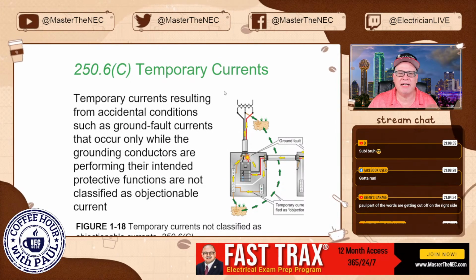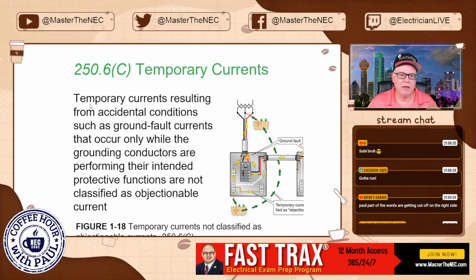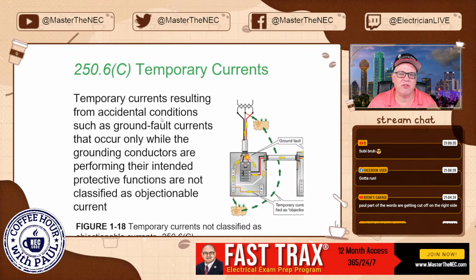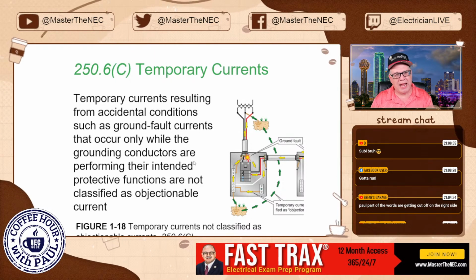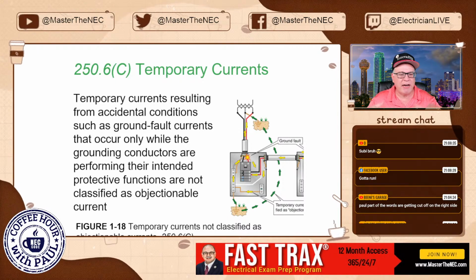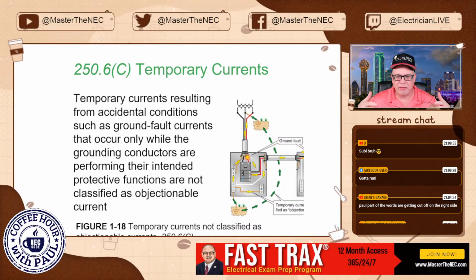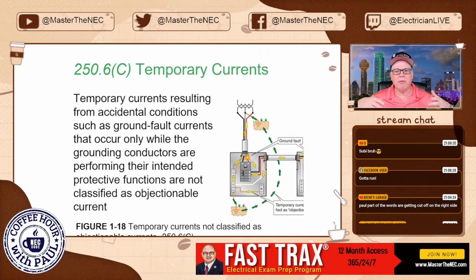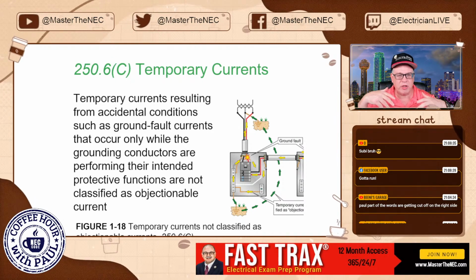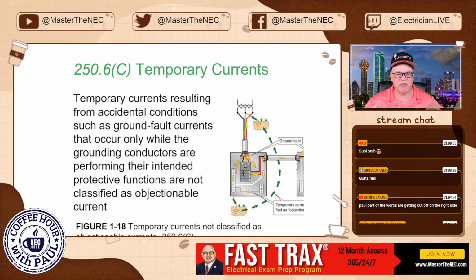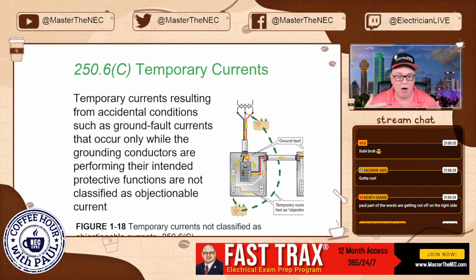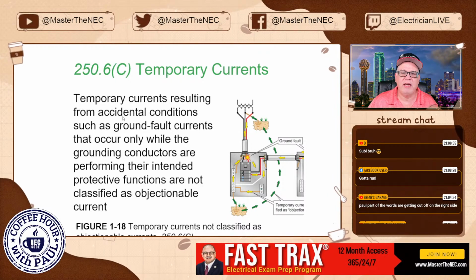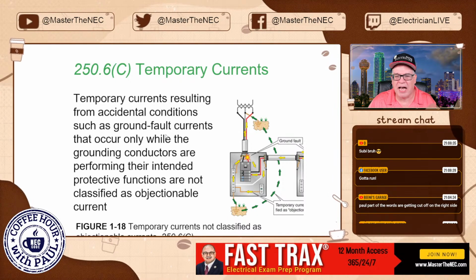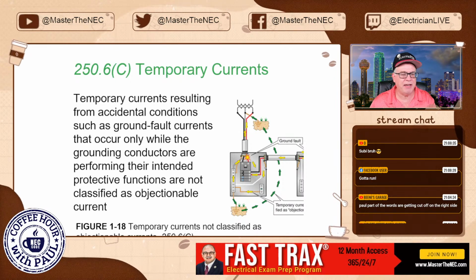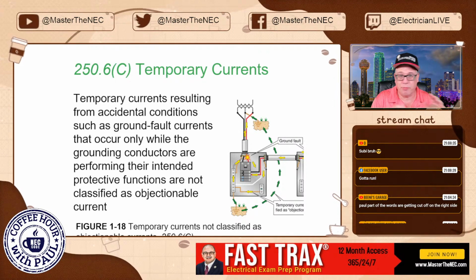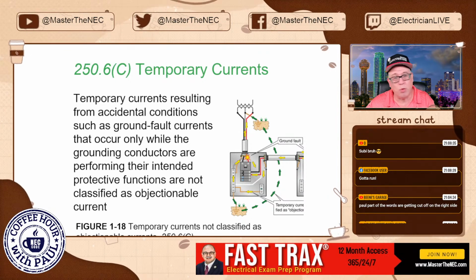All right, temporary currents, 250.6(C). Temporary currents resulting from accidental conditions such as ground fault. So this is what happens when you know that the raceways are not designed to be current carrying. They're non-current carrying metal parts. But under a fault, when a ground fault occurs, and now we have an accidental condition where ground fault current is now going to be on this equipment. So these are called temporary currents. They're not objectionable current. They're happening hopefully very briefly, and then a breaker will clear or a fuse will blow.